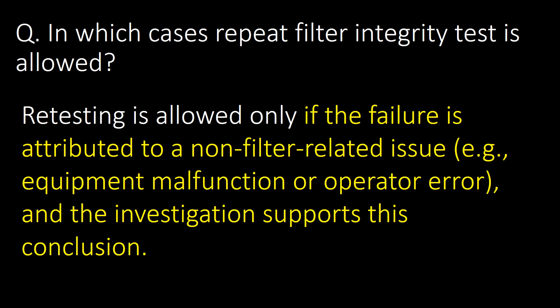In which cases is a repeat filter integrity test allowed? Retesting is allowed only if the failure is attributed to non-filter-related issues, such as equipment malfunction or operator error, and the investigation supports this conclusion.